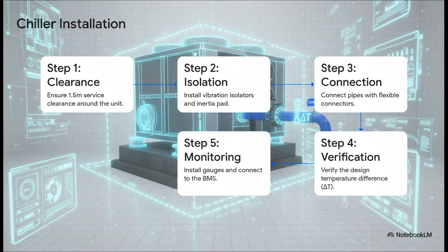Then step 2, the isolation. This is absolutely crucial. That huge concrete inertia pad and the spring isolators underneath it absorb the machine's vibration so the entire building doesn't have a constant, annoying hum. Only after that's perfect do you move to step 3 and connect the main pipes. And finally, you get to steps 4 and 5, which are all about checking your work and hooking it up to the building's brain, making sure it's hitting its temperature targets and communicating properly. You have to get this sequence exactly right.